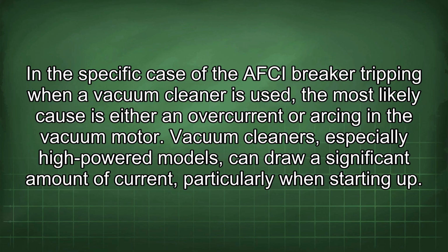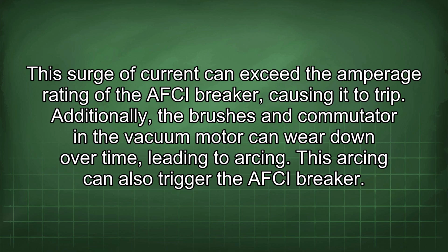most likely cause is either an overcurrent or arcing in the vacuum motor. Vacuum cleaners, especially high-powered models, can draw a significant amount of current, particularly when starting up. This surge of current can exceed the amperage rating of the AFCI breaker, causing it to trip. Additionally, the brushes and commutator in the vacuum motor can wear down over time, leading to arcing. This arcing can also trigger the AFCI breaker.